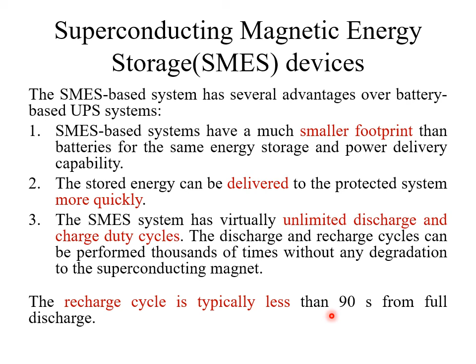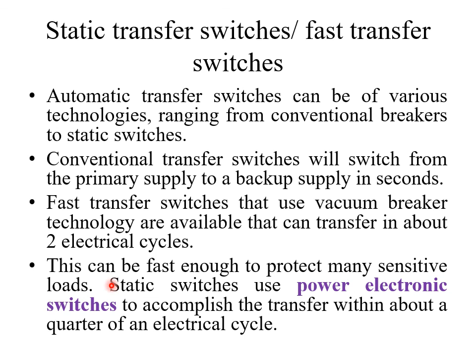Static or fast transfer switches. The transfer switch switches the source, maybe the primary source to the secondary source or the secondary source to the primary source. Conventional transfer switches will switch from primary to backup, and it will take some seconds, whereas fast transfer switches can transfer in about 2 electric cycles. That means it is less than a second, and this is due to the advancement of power electronic technology.